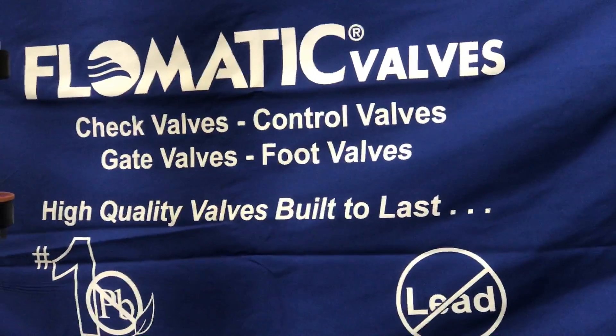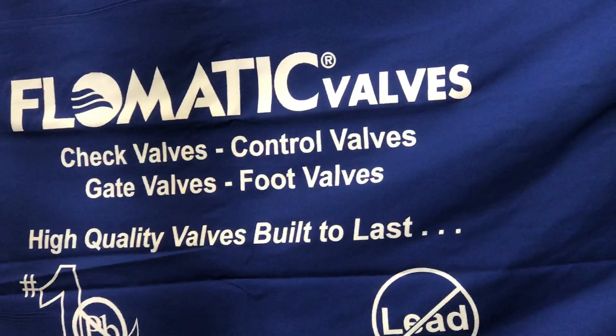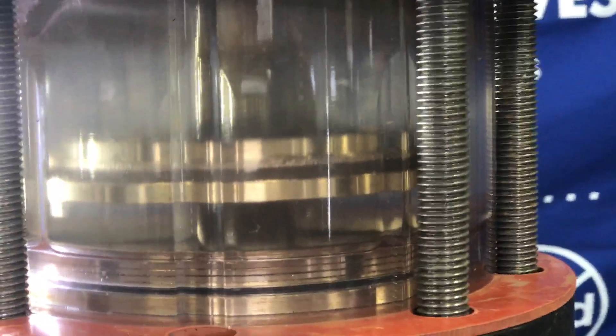This is another test report from Flomatic on wafer style check valves. We have here a four inch wafer style check valve which is built of a traditional double guided disk, at around 250 gallons a minute, which would be normal flow. As you can see, the disk is moving back and forth and you can hear a slight noise.